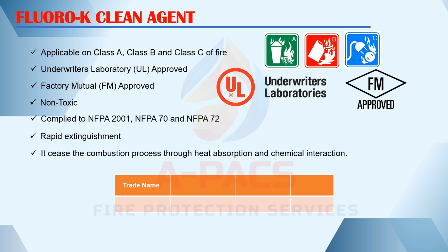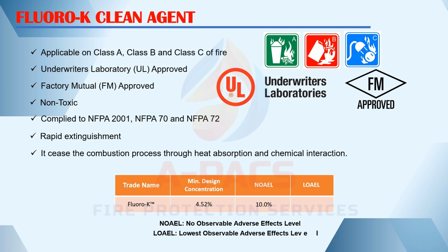Trade name: Fluoro-K. The minimum design concentration is 4.52%. The NOAEL is the No Observable Adverse Effects Level, 10% Adverse Effects. And the LOAEL is the Lowest Observable Adverse Effects Level, greater than 10% Adverse Effect.